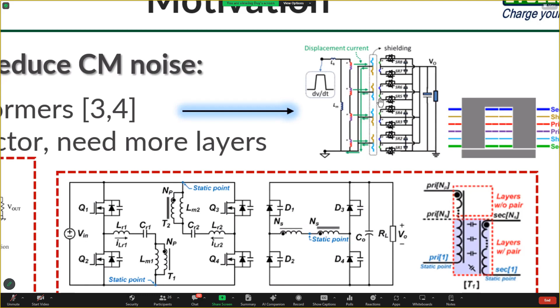For the second question about the connection terminal of the shielding - actually the shielding can connect to the ground of the primary side or the ground of the secondary side. We just have to guarantee that the gradient voltage matches: if we connect to the primary side, the gradient voltage of the shielding and the secondary side have to be the same, to avoid a displacement current from the shielding to the secondary side, which would create common mode noise.